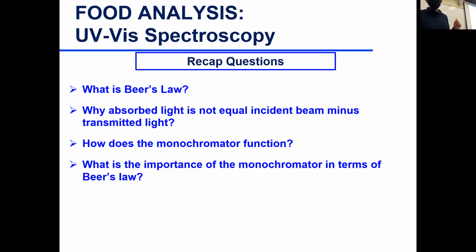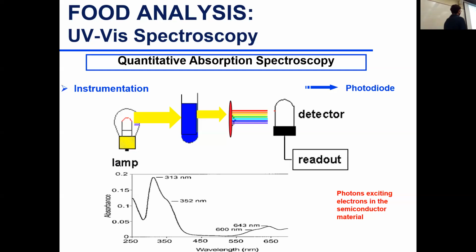Great. So last time I introduced one type of UV detection using a monochromator. Now today I'm going to continue with the photodiode array detector, which you had in HPLC. I told you what it does, but I didn't tell you how it does it. So basically with the photodiode array detector, you get a scan of absorption over a wide range of wavelengths. So how does this work now when you get a spectra, a fingerprint? How does it work?